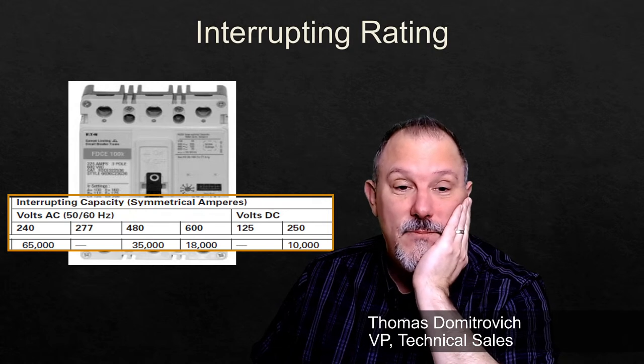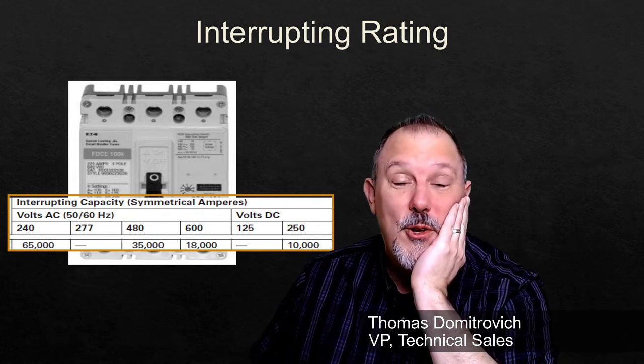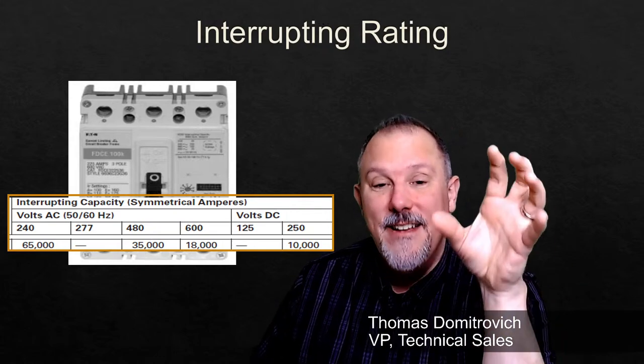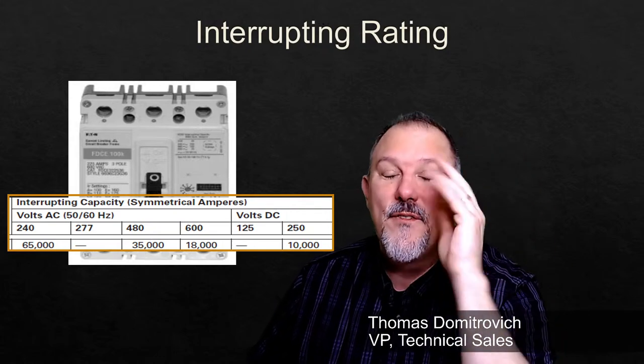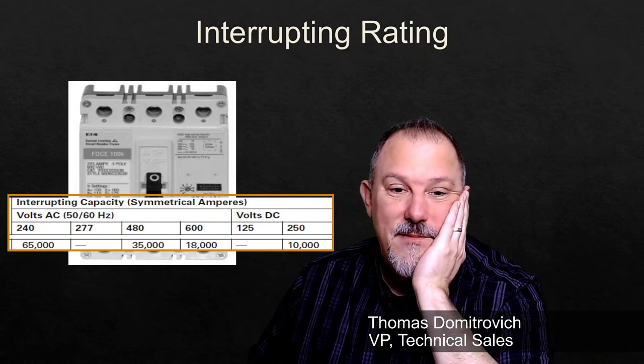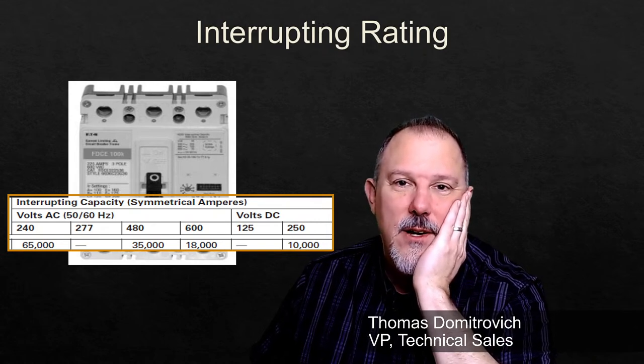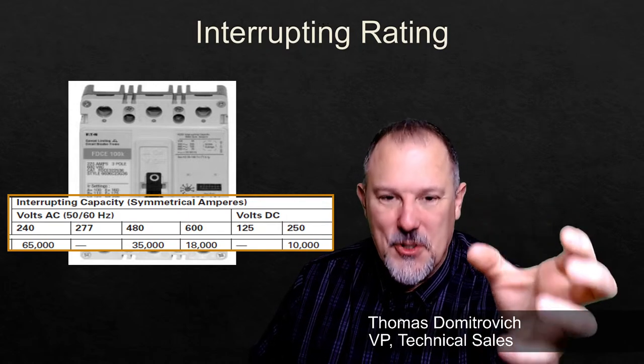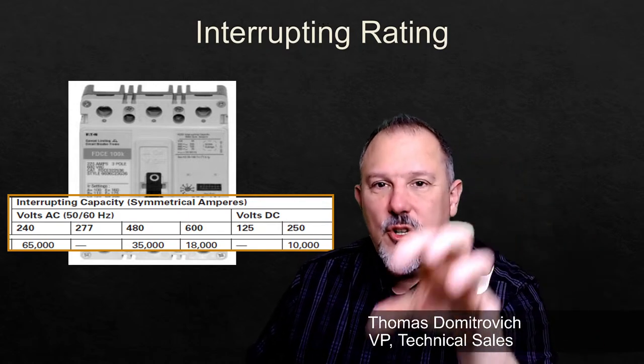I said, hey, at breakers, where are you using them? He said 480 volts, and I showed him the literature. It's only rated for 35. And there was dead silence on the phone. He goes, oh my gosh, I can't believe I missed that. But you get into those situations, voltage is critical with a circuit breaker.